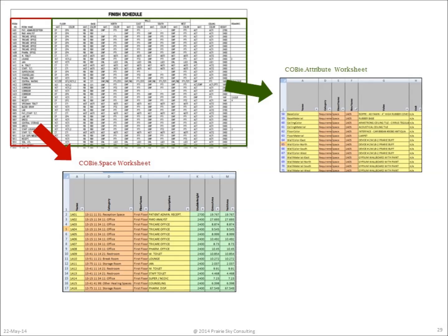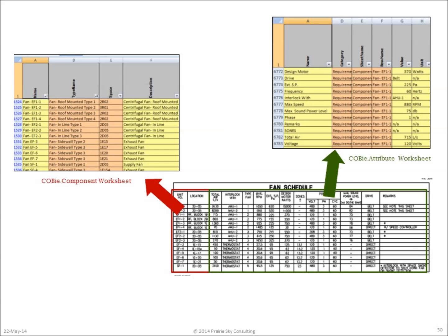In this example, we'll use the spreadsheet version of COBie since the transformation is very straightforward. Here we see a finished schedule in the upper left-hand part of this slide, and the finished schedule is composed of two parts: the list of spaces or rooms in the building, which are transferred to the COBie space worksheet, and the properties of each of those spaces, which are provided in the COBie attribute worksheet. In a second example, we have a fan schedule in the bottom right-hand side of the slide. That fan schedule is decomposed into a COBie component worksheet, which lists each piece of equipment, its type and where it's located, and then the design attributes for that equipment, which are identified in the COBie attribute worksheet.